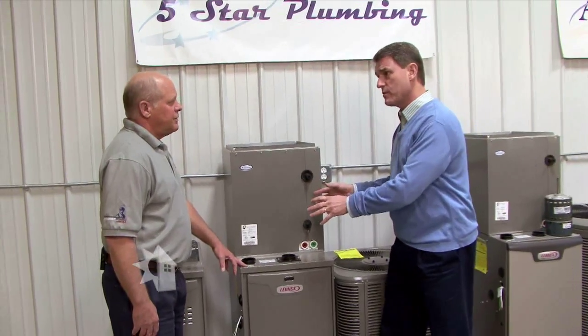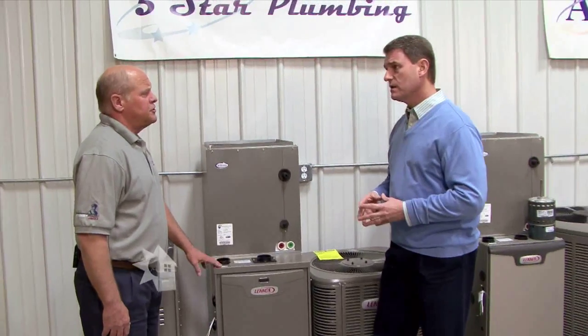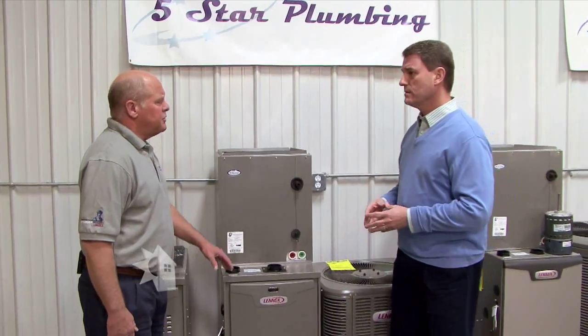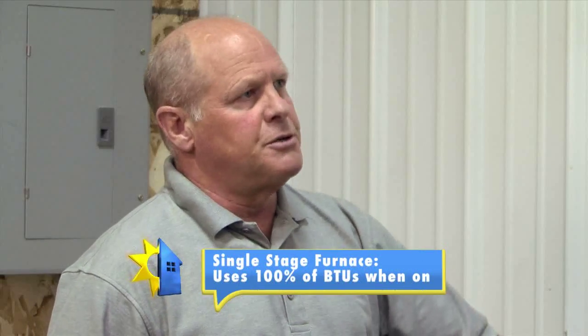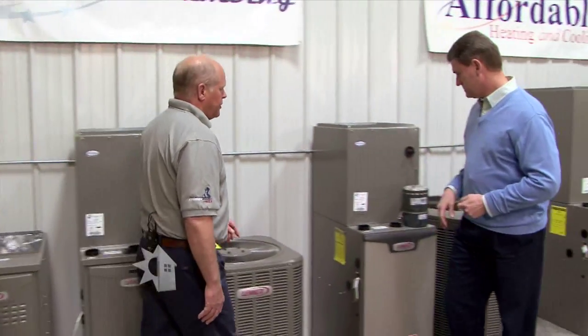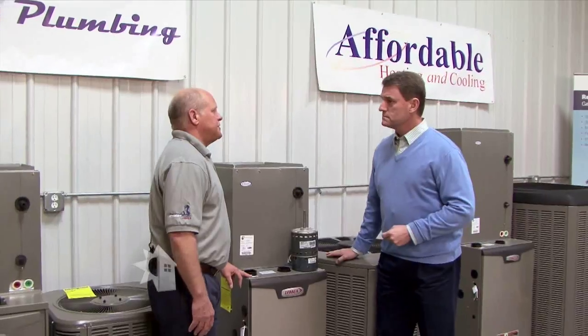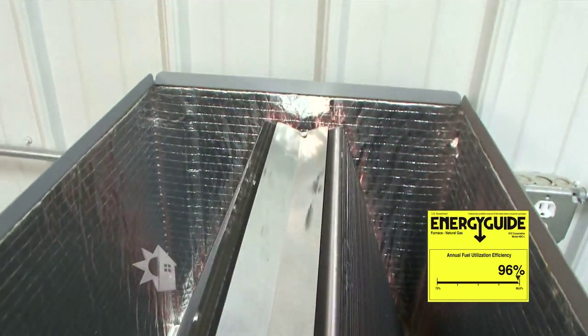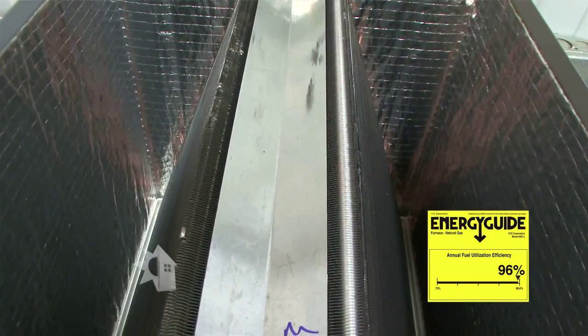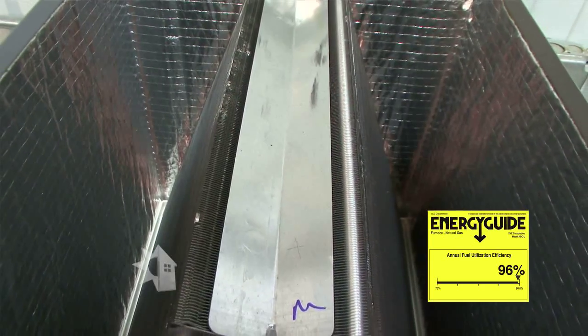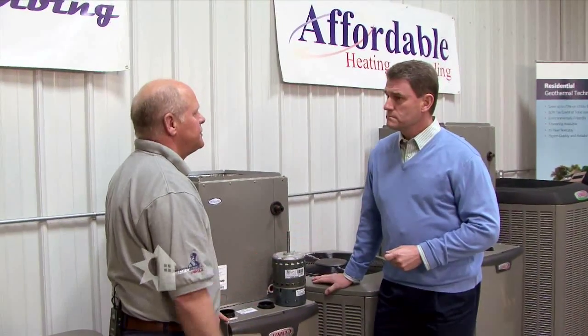And you still sell quite a bit of this? We sell a large amount of single stage products. What that really means is on a call for heat, you get 100% of the rated BTUs firing at the same time. Whereas with two-stage products, you get two firing ranges: a low fire and a high fire. The theory is that it gives more even heat, keeping the comfort zone in your house a lot longer. The other part of this product is the high efficiency motor.